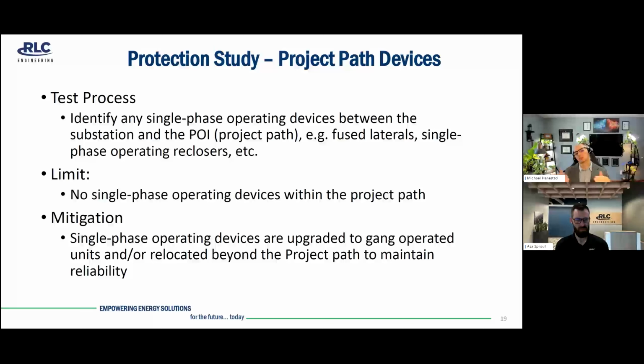So if your project is right below a midline recloser that was single phase operating, you might be able to just shift that down. Or if your project is right below a fuse, that fuse might be able to be relocated just downstream of the project without the need of a new device, assuming it's not impacting reliability.